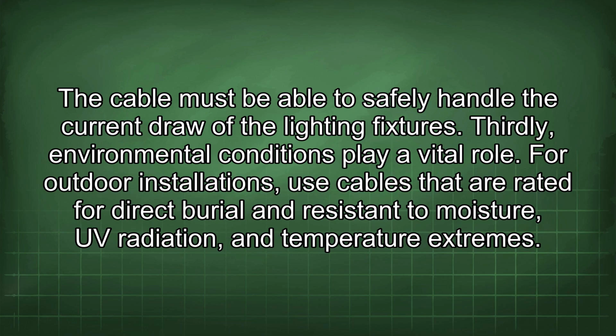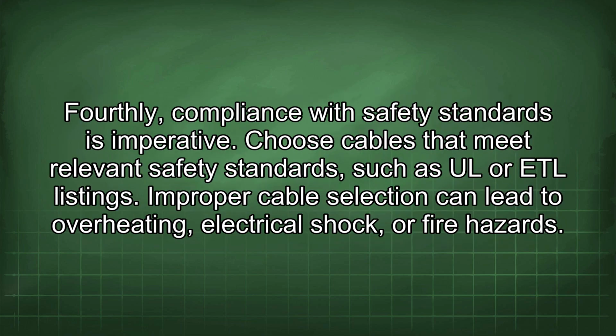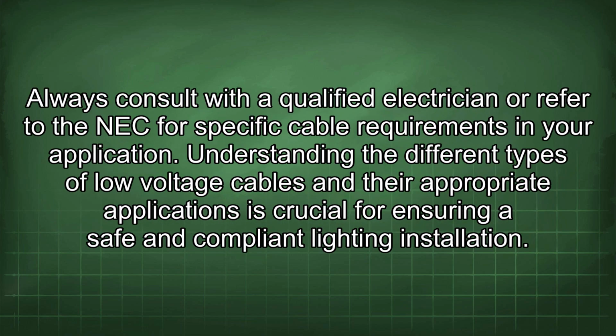Thirdly, environmental conditions play a vital role. For outdoor installations, use cables that are rated for direct burial and resistant to moisture, UV radiation, and temperature extremes. Fourthly, compliance with safety standards is imperative. Choose cables that meet relevant safety standards such as UL or ETL listings. Improper cable selection can lead to overheating, electrical shock, or fire hazards. Always consult with a qualified electrician or refer to the NEC for specific cable requirements in your application. Understanding the different types of low-voltage cables and their appropriate applications is crucial for ensuring a safe and compliant lighting installation.